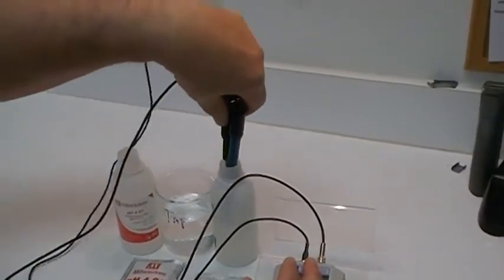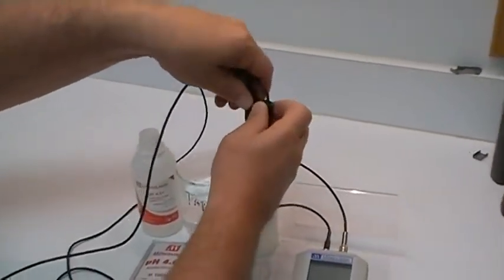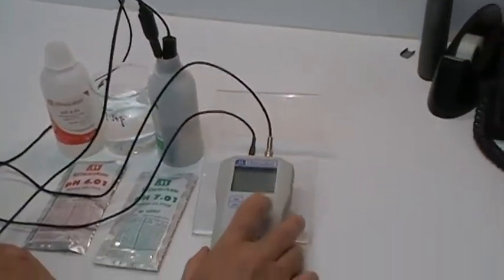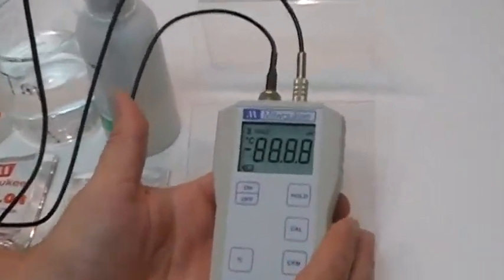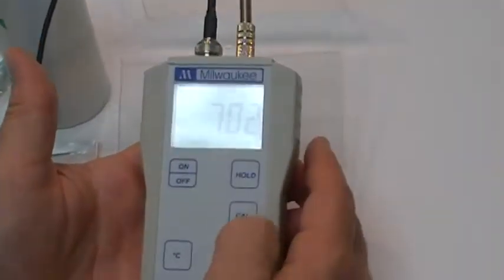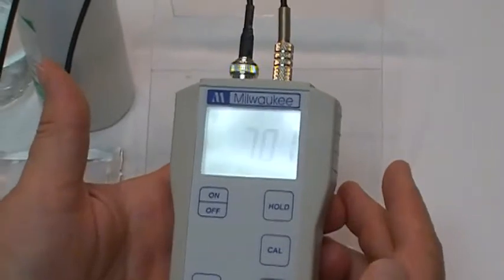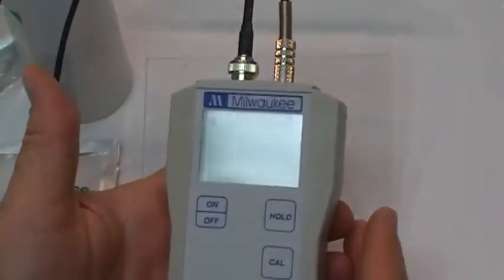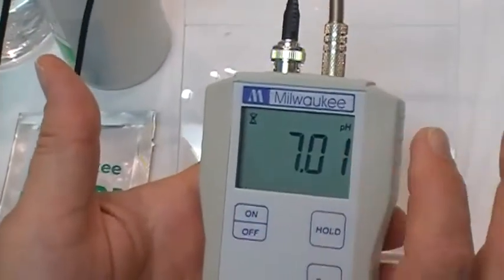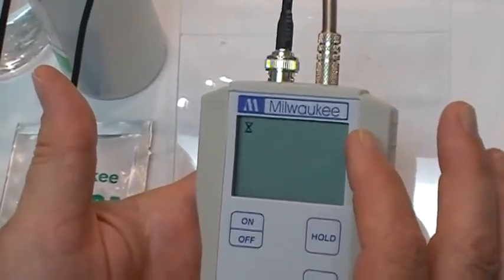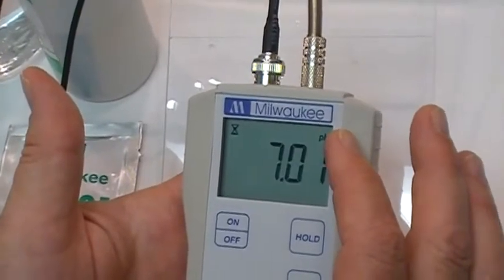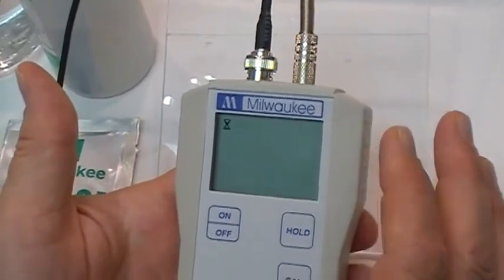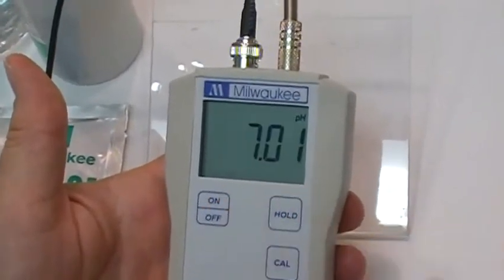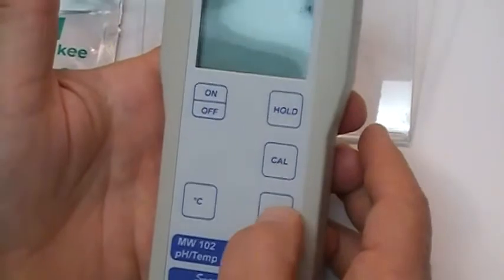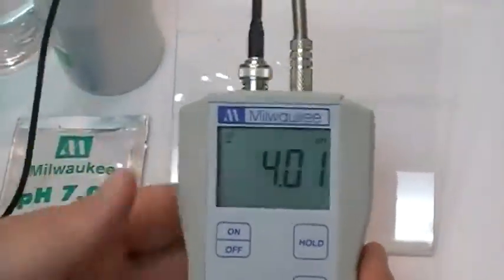So, to get started, we're going to insert the pH probe and the temperature probe together into the calibration standard that we have and turn the unit on and go into the calibration mode by hitting the cal button. You're going to see the flashing. In your instructions it says look for the pH tag to stop blinking. They are referring to the pH in the upper right hand corner letters, pH, that, as you'll notice in just a minute. Then there you go, the numbers will continue to blink. The pH stopped blinking. At this point you hit the CFM button.